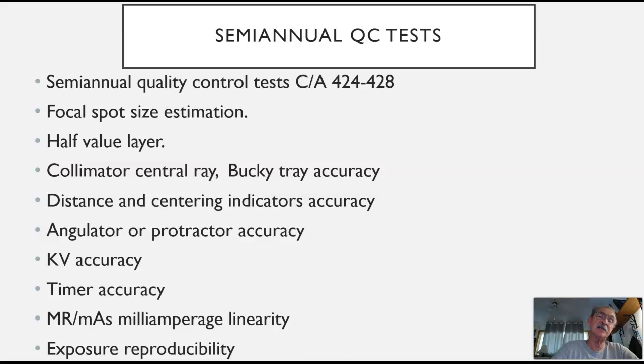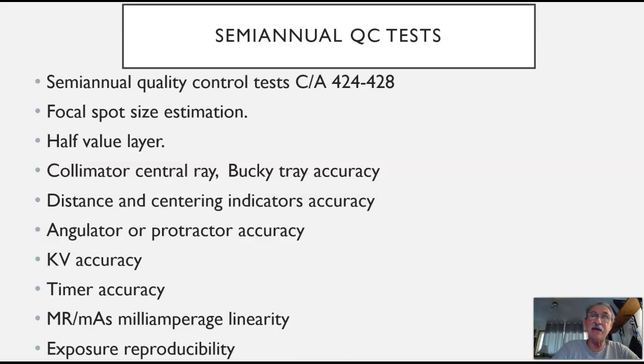So if we're selecting 50 KV at 10 milliseconds, for instance, we have proof positive based on these meters that that is in fact what we selected and what the output was. Milliampere linearity — linearity is similar to reciprocity. One second at 10 MA would be a 10 MAS exposure, but half a second at 20 MA would also be a 10 MAS exposure. We want to be sure that our milliampere stations are set up so there is no discrepancy between them — that they're accurate and predictable.